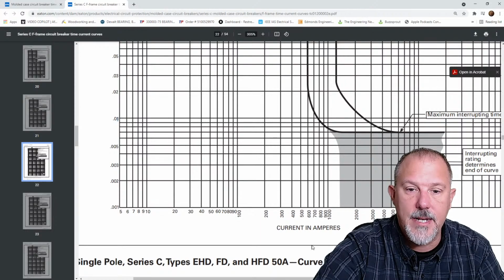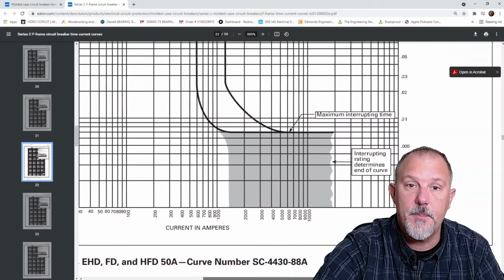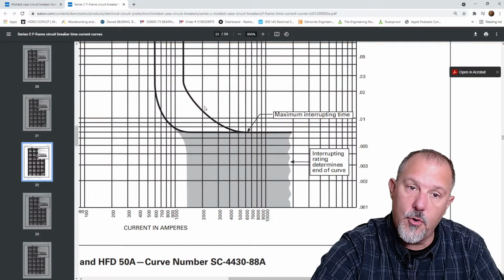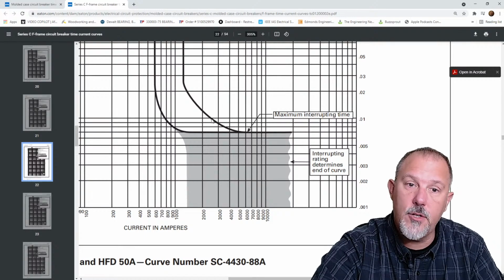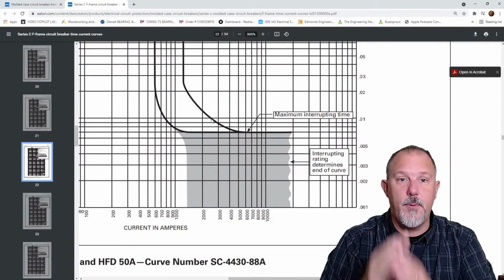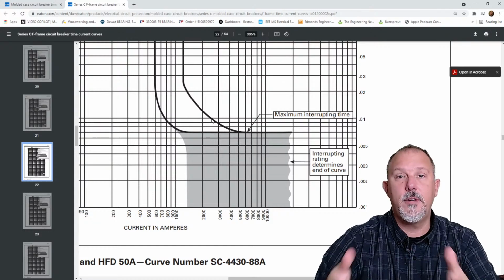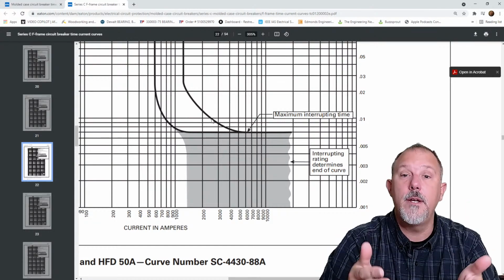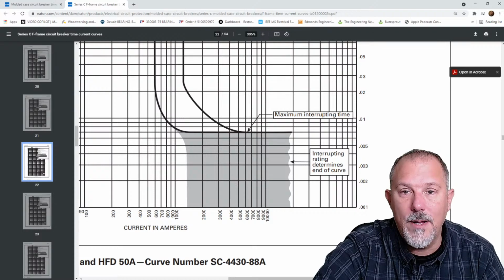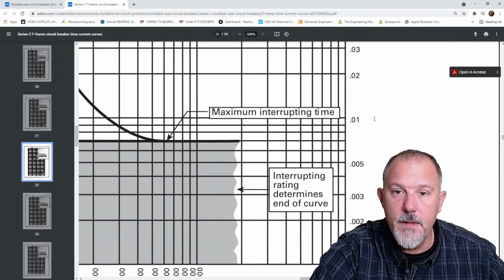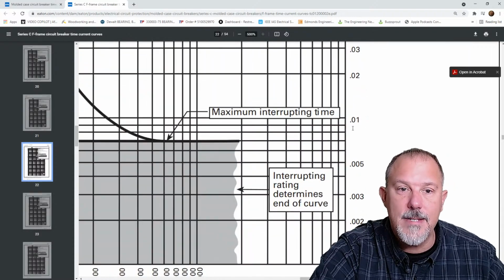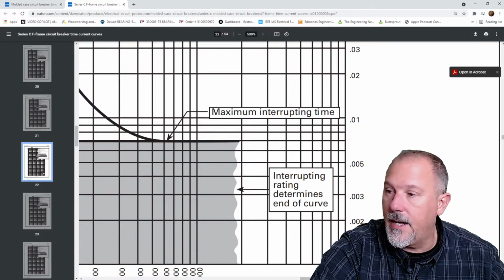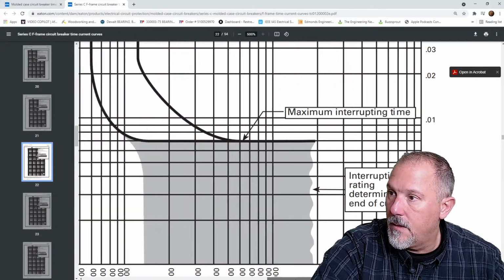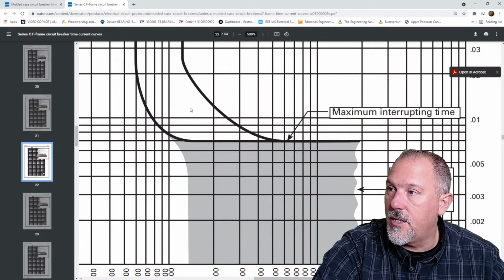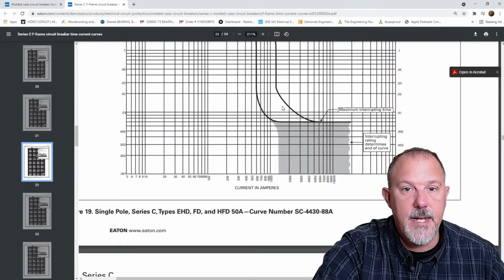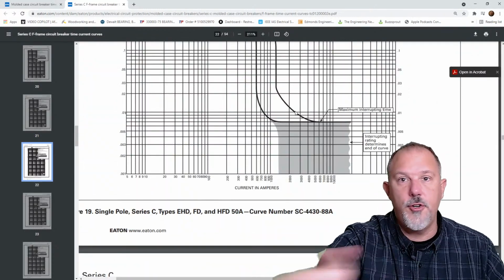There's my 0.01 seconds. If I plotted a 50 amp circuit breaker, it would cross over and basically get cut off at the bottom of a time current characteristic curve if it was cut off at 0.01 seconds, which is right here. Look, that says 0.01 seconds. That is where it would cut off. You would see the curve, the instantaneous, cut off right there, and it wouldn't show you anything past that.